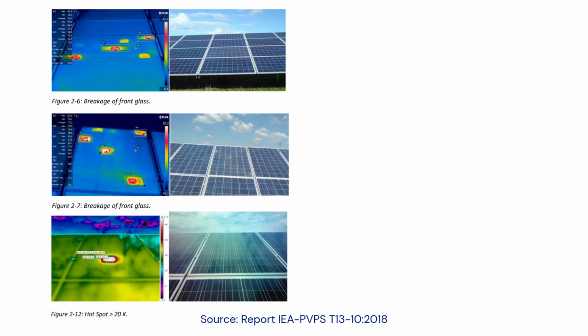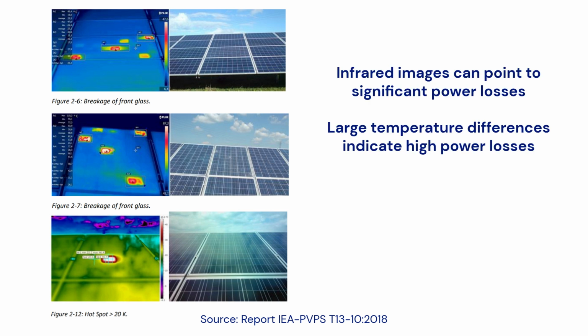If monitoring data are available, they can support the interpretation, although their accuracy is limited by the inverter. In complex installations, for example on industrial rooftops with different roof layouts, varying string lengths, and different orientations or tilt angles, monitoring data often show large scatter and do not clearly indicate defective components.